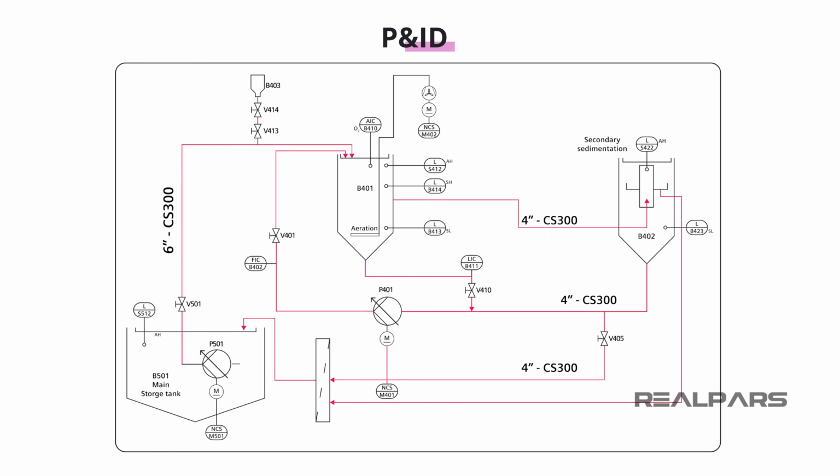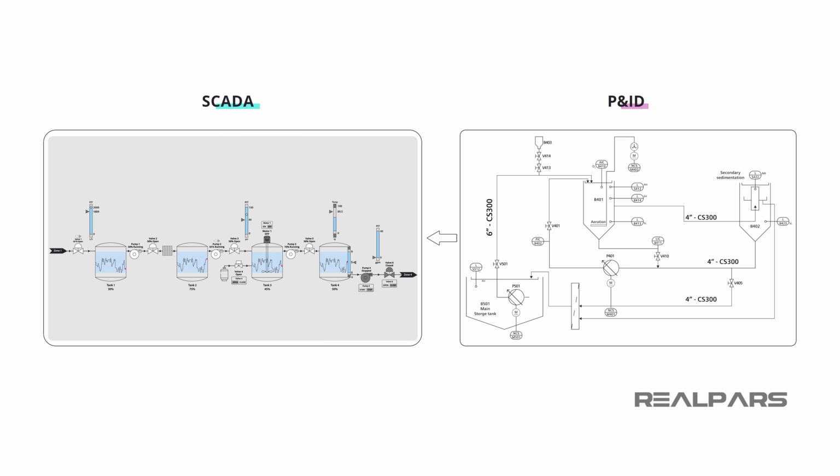These drawings would show the piping layout with pipe sizes, the location of instruments, valves, motors, etc. within the piping, as well as symbols indicating what signals will be passed to and from the processors in the system. The controls engineer would take those P&IDs and create a group of graphical screens that would contain all pertinent information that an operator may need to interact with and control his or her water treatment system.